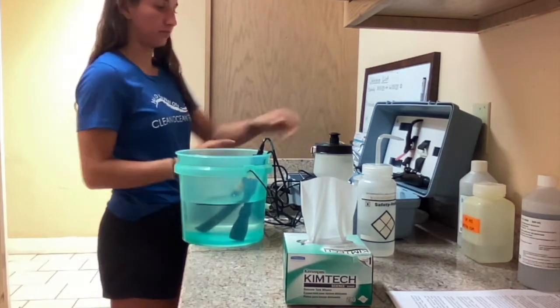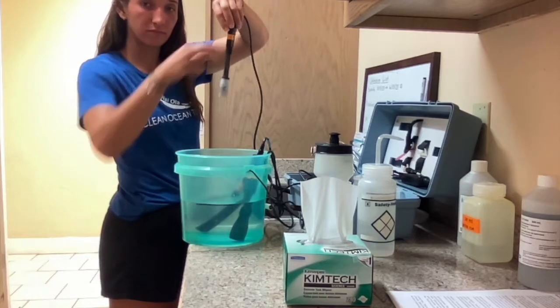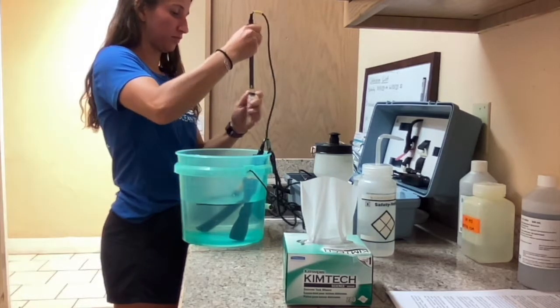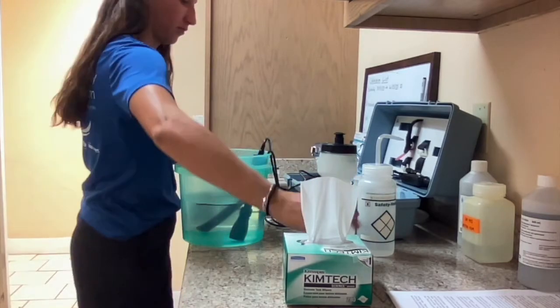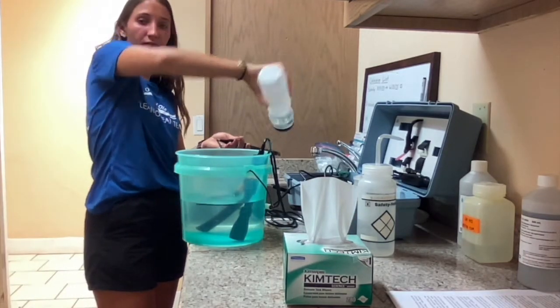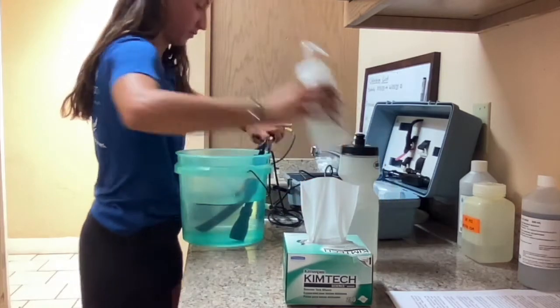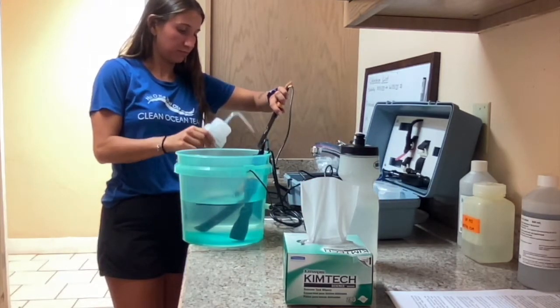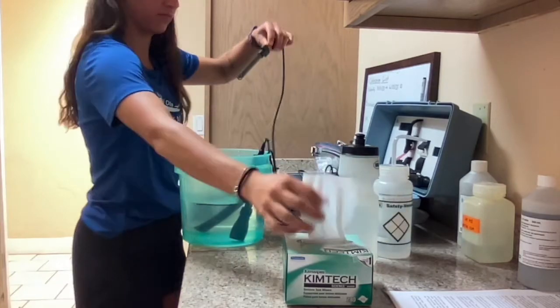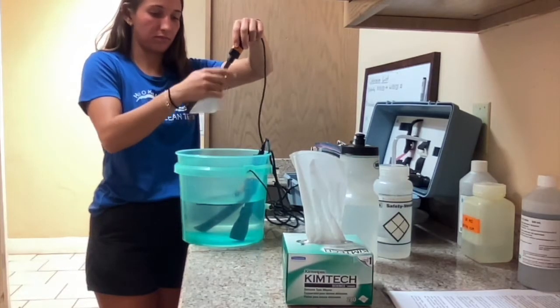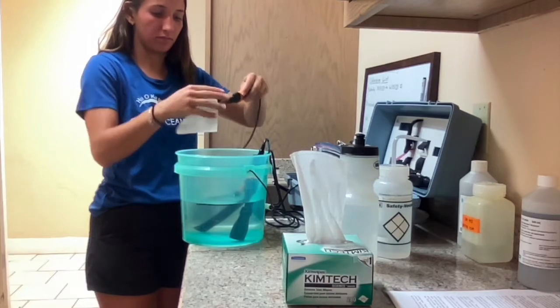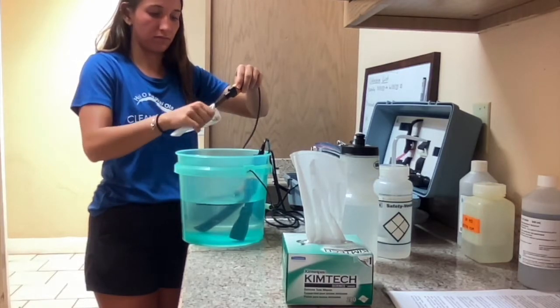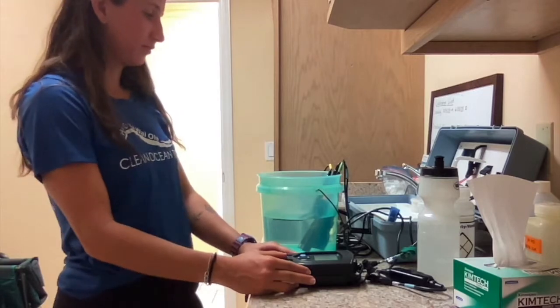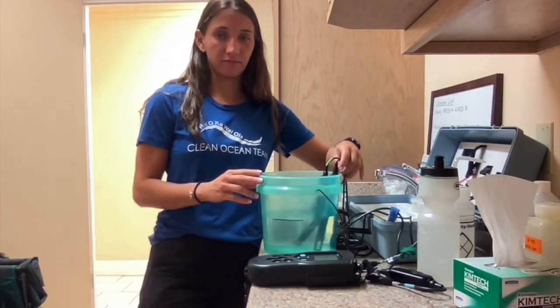Before you put the pH probe in the water, rinse the probe first with tap water and then distilled water. And then dry the probe with Kim wipes. This step is important because the pH probe was stored in a concentrated KCl solution which could contaminate the water. Once all of the probes are in the bucket, soak them for at least 2 minutes before taking measurements.